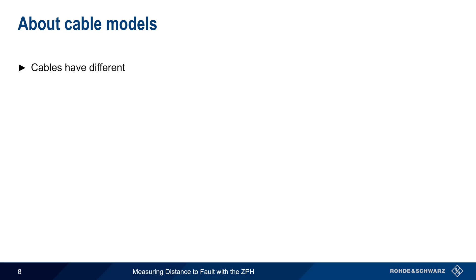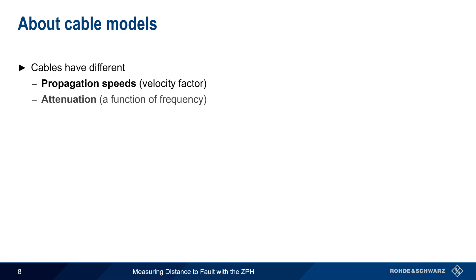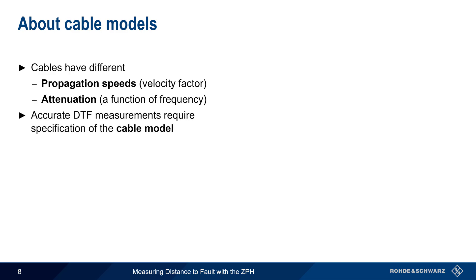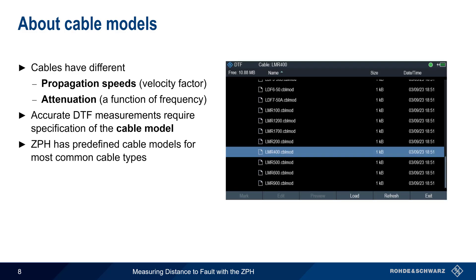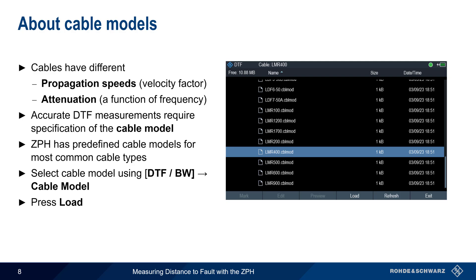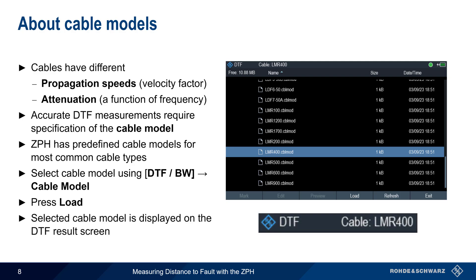The next step is specifying a cable model. Coaxial cables with different conductor spacings and different dielectrics will propagate signals at different speeds. This is called the velocity factor of a cable. They will also have different amounts of attenuation, which is a function of frequency. Therefore, accurate distance to fault measurements require the specification of a cable model, which describes both the velocity factor and the frequency-specific loss of the cable under test. The ZPH comes preloaded with a large number of models for the most common cable types, which can be chosen using DTF Bandwidth > Cable Model and then pressing Load.